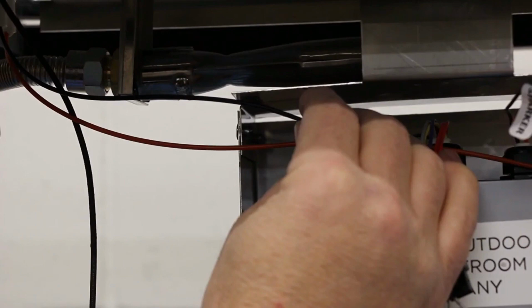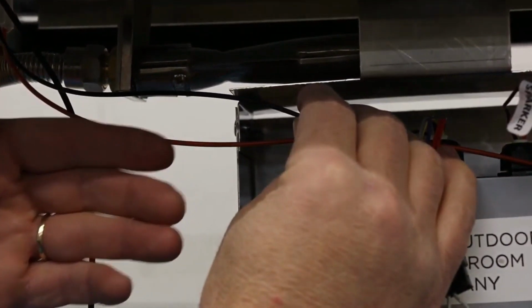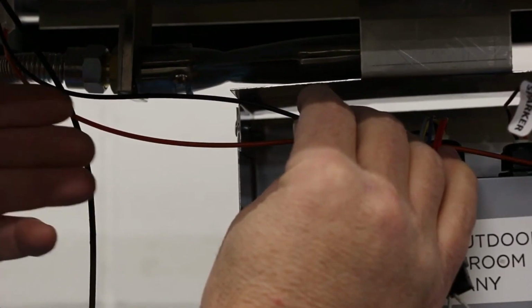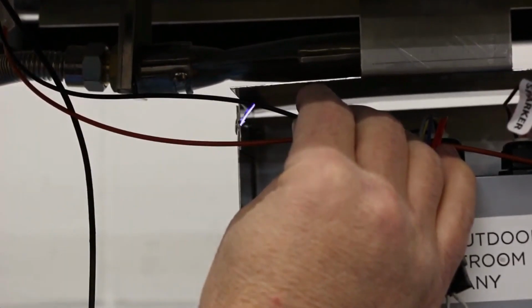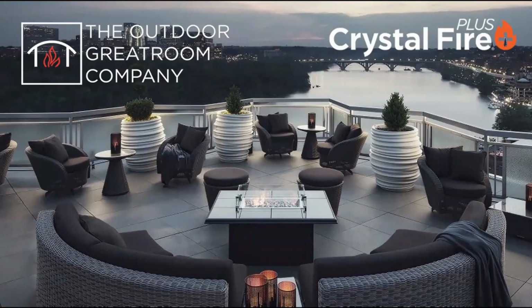Electrical flow will always take the path of least resistance. Follow the igniter wire under the burner to see if you can see it sparking. It is possible the insulation on the wire was nicked and causing the spark to occur somewhere other than the igniter area. If this is occurring, repair the wire with some electrical tape or order a new electrode. And this completes all the steps to assure you have proper spark on your DSI burner system.